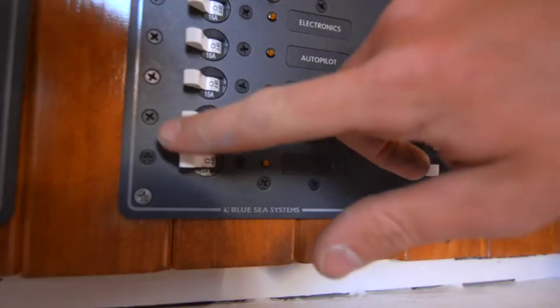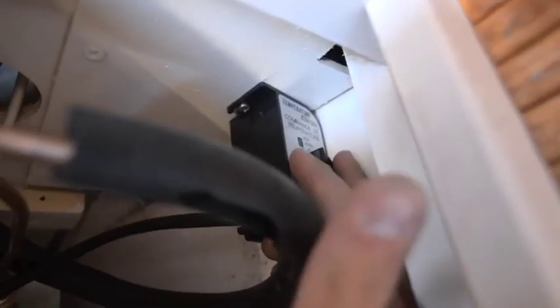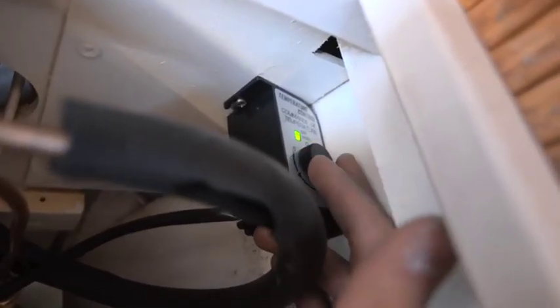Turn on power from the panel and turn on the temperature control dial. After a few minutes, the evaporator plate should feel cold, indicating circulation of refrigerant. Check both AC and DC operation.